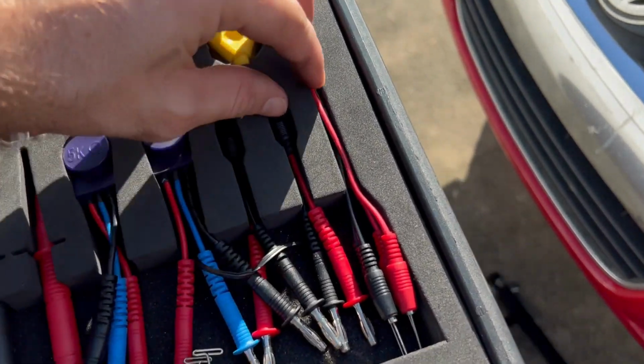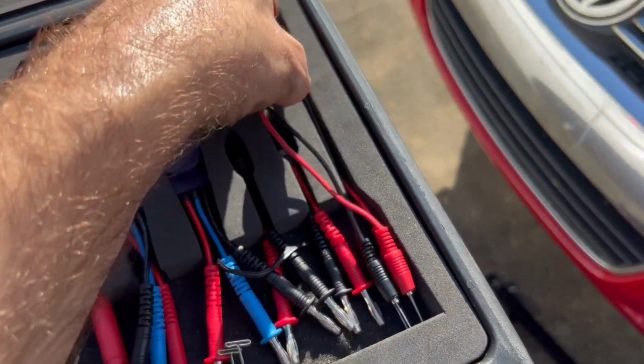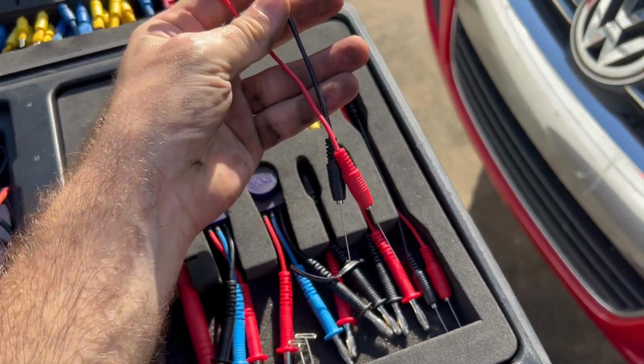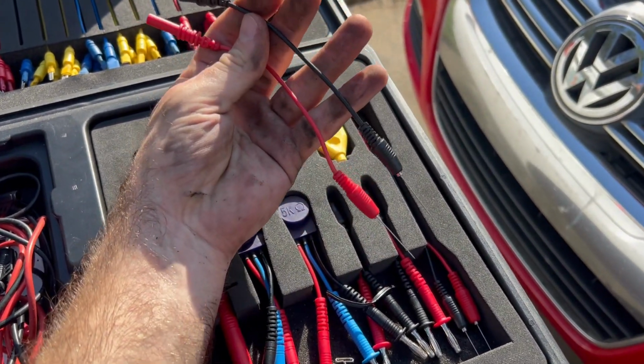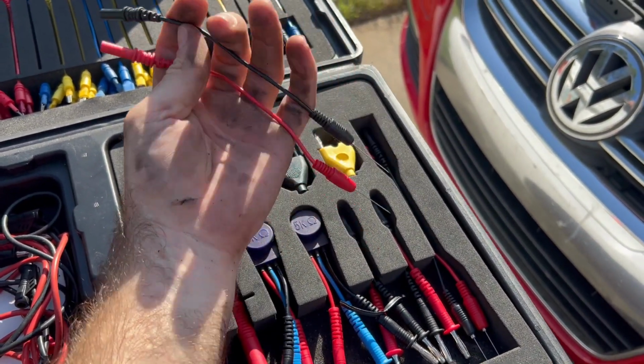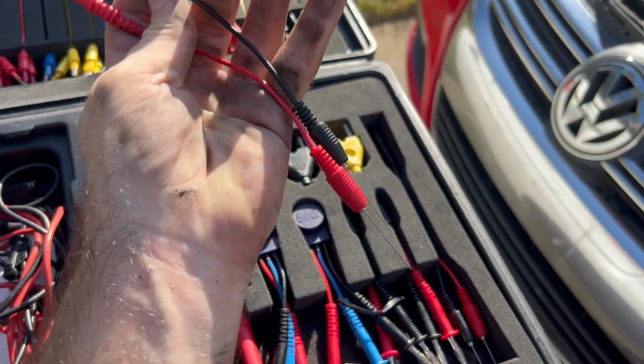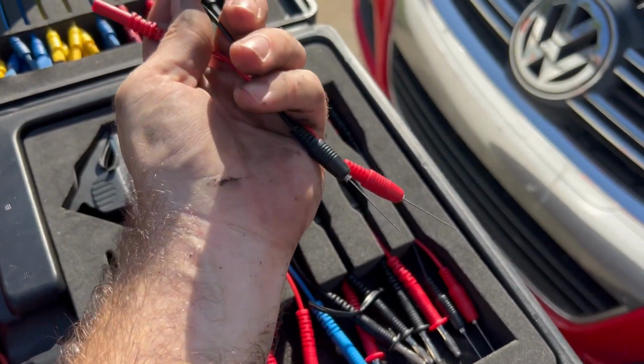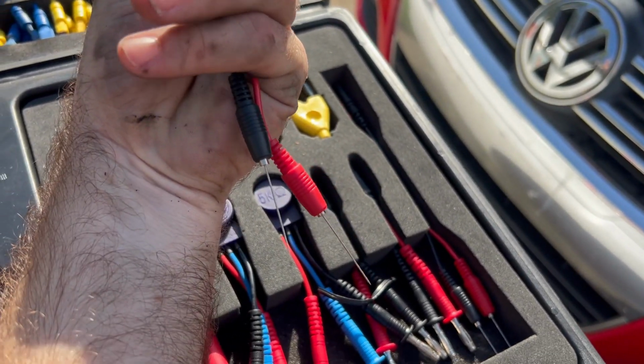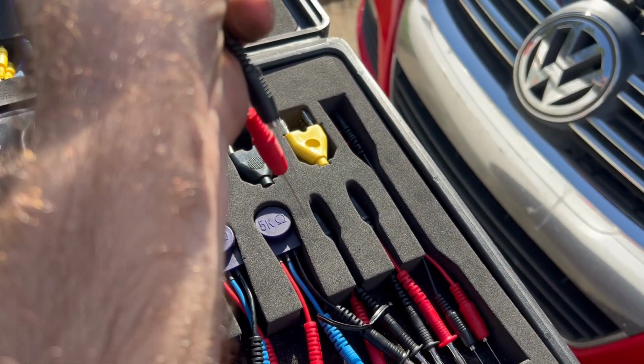These are super handy for back probing, and this is what we'll use today for testing the voltage at the refrigerant control valve. You just plug them into the leads here, plug them into the meter, and then back probe the connector, so you don't have to worry about shorting the connector together.